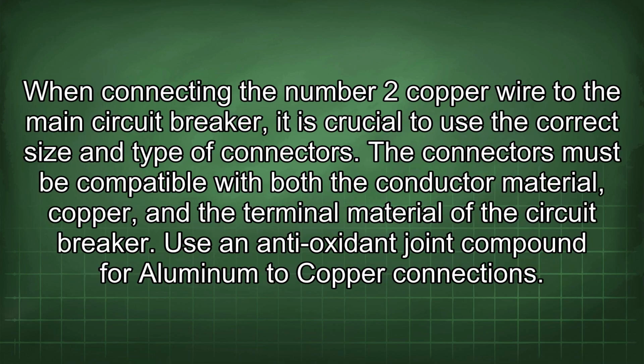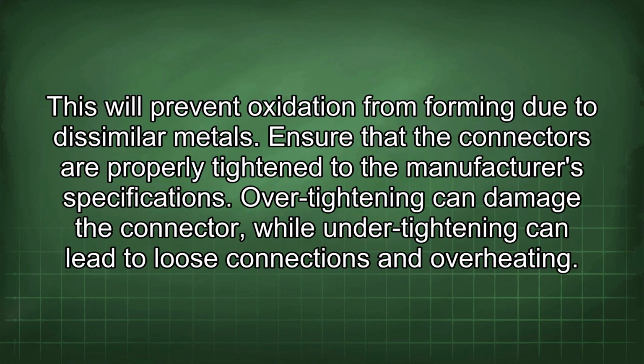When connecting the number 2 copper wire to the main circuit breaker, it is crucial to use the correct size and type of connectors. The connectors must be compatible with both the conductor material, copper, and the terminal material of the circuit breaker. Use an antioxidant joint compound for aluminum to copper connections. This will prevent oxidation from forming due to dissimilar metals. Ensure that the connectors are properly tightened to the manufacturer's specifications. Over-tightening can damage the connector, while under-tightening can lead to loose connections and overheating.